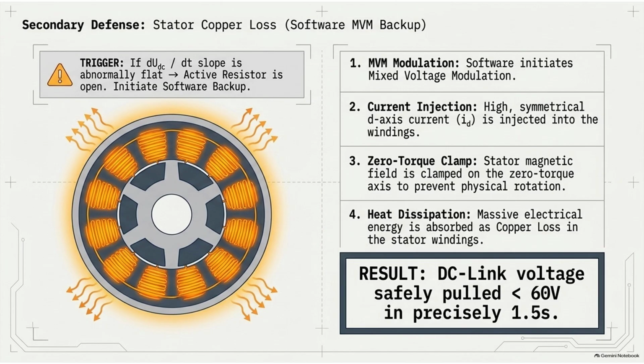They specifically inject what is known as a direct axis current. This creates opposing magnetic forces inside the motor that cancel each other out. It actively traps the magnetic field at a state of absolute zero torque, so it can't move. Exactly, the motor is magnetically locked and cannot spin no matter how much power you dump into it.